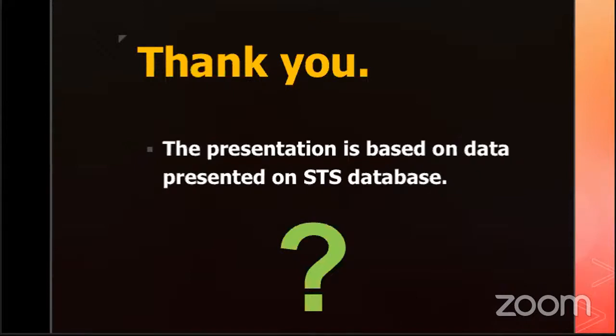Unfortunately, it's very, very difficult to answer that question. Sometimes a valve gets introduced into the market with very short follow-up, mostly in animal studies that are extrapolated to humans. Many of them have been introduced and used, and then with clinical use they fail miserably. A historical example is the Ionescu-Shiley bovine pericardial valve, which when introduced was the valve of the future. But unfortunately, it failed, people stopped using it, and it was withdrawn from the market.